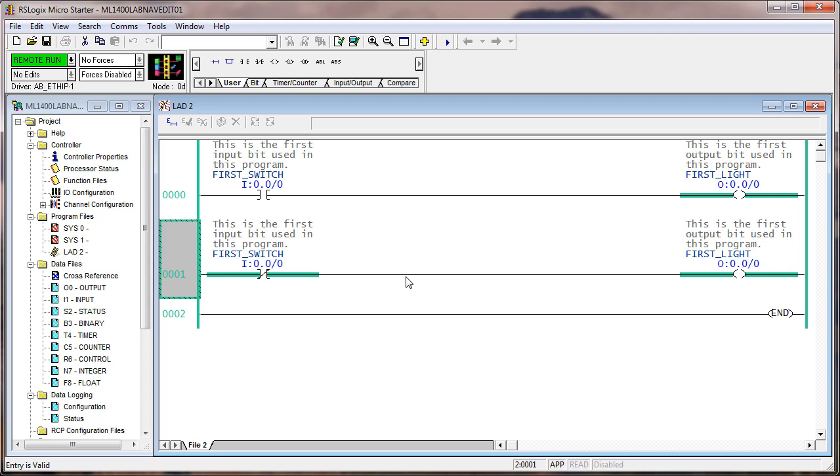Now is where we discuss what we're looking at here. I show the switch off right here, and we know that because the bottom instruction is true if off. If I flip the switch on, now this instruction is true, but it shows the bit off because last man wins. This instruction is false, so it turns this bit off. Even though that rung is true, it is setting that bit, but microseconds later, after it's set the bit to 1, it's setting it to 0.